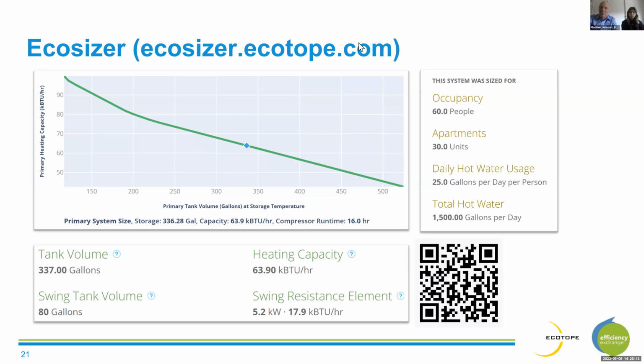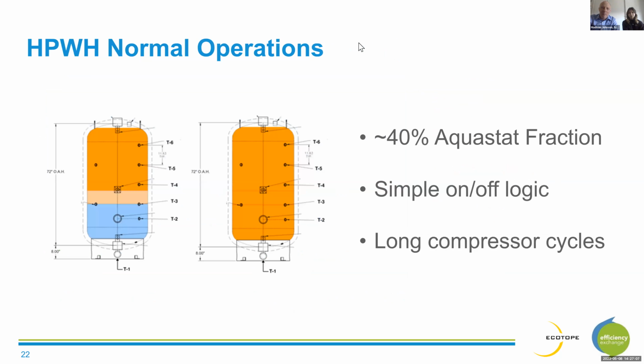The gas system has a relatively small amount of hot water storage and a relatively big gas burner so that it can recover really quickly. The more cost-effective way to do heat pump systems is a large amount of storage that enables you to coast through those peak periods and relatively small heat pump capacity.